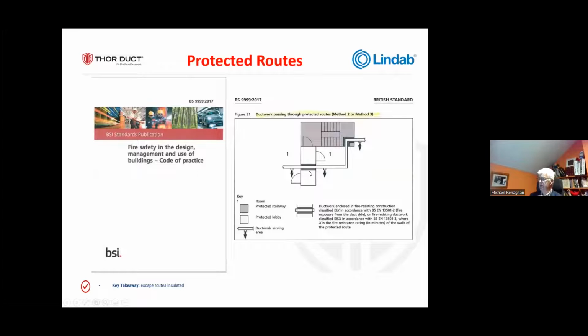When it crosses a protected route and you're not using a fire damper in the ventilation system, now very often you can't because it's apartments and etc. When you don't use it, you must use fire resisting duct, and the portion that is contained inside the fire compartment must be insulated.